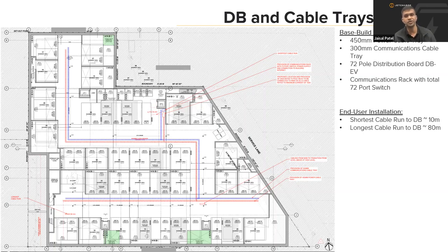And this allows for the voltage drop and the cable sizes changing based on how far the run is. So the shortest cable run from the distribution board to the EV charger is about 10 meters. And the longest cable run is 80 meters, which is just within the constraints of our 90 meters Category 6 run to the comms rack. So the line in blue represents the communications cable tray, and the line in red represents the power cable tray. The power cable tray is obviously 450 mil. The communications cable tray is 300 mil.